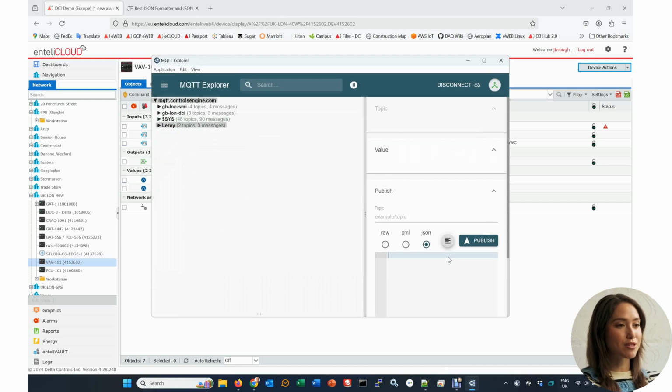Remember what I said about UDMI schema managing the device telemetry from the cloud side? So when a UDMI device connects, it subscribes to a specific topic, as defined by UDMI, called the config. This tells the device what to publish and when and whether it needs to act as a proxy for other non-UDMI devices on the network. So we need to put the appropriate message into the broker so that when the device subscribes, it gets sent down and the device knows what it needs to do.